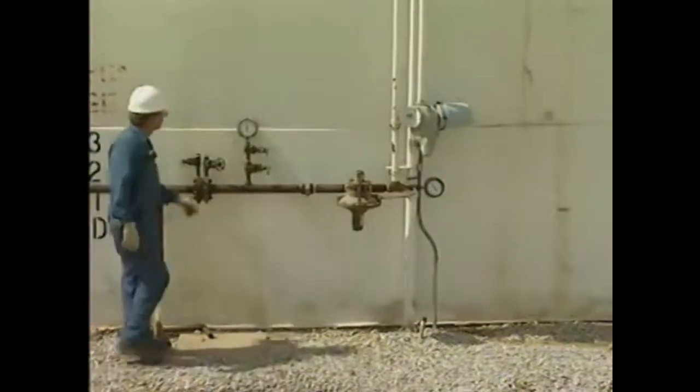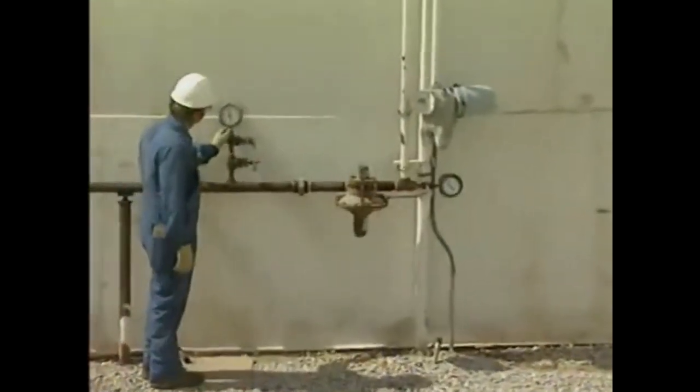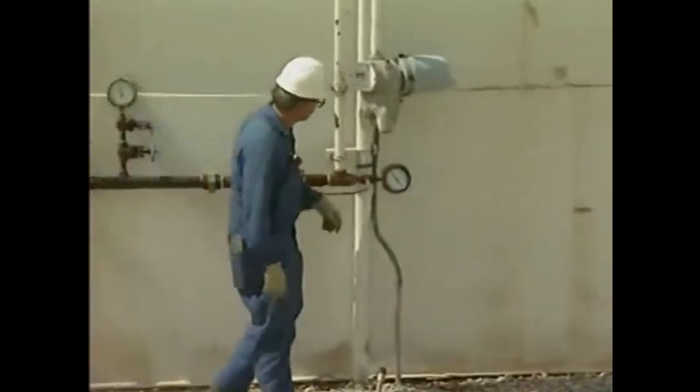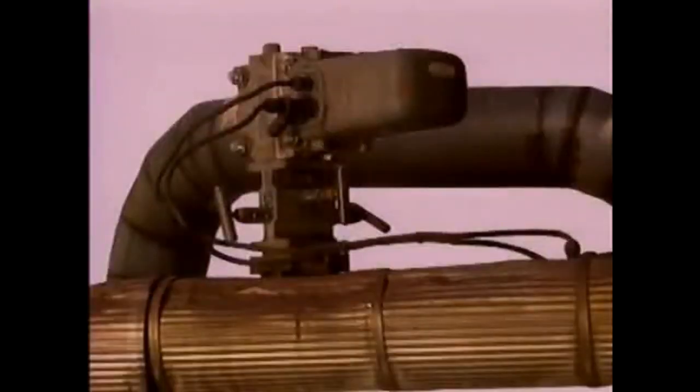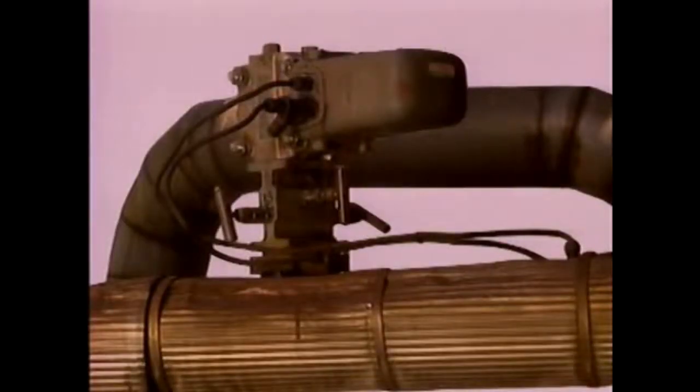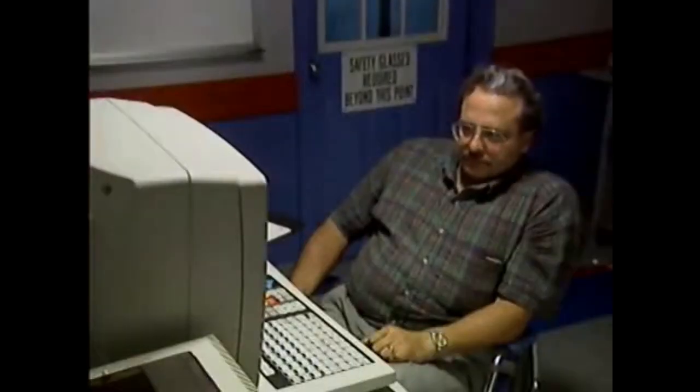The nitrogen supply lines are checked for any signs of damage. There are no signs of leaks in the nitrogen supply. The outside operator isolates the rotometer from its supply of nitrogen. After completing the isolation, he calls the control room and informs the operator of his actions. At this point, the rotometer is isolated, but the reason why the rotometer was not operating properly has not been determined. To continue troubleshooting, the operators decide to unisolate the rotometer.